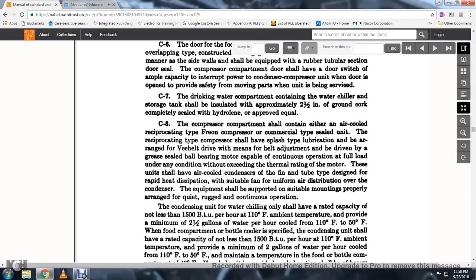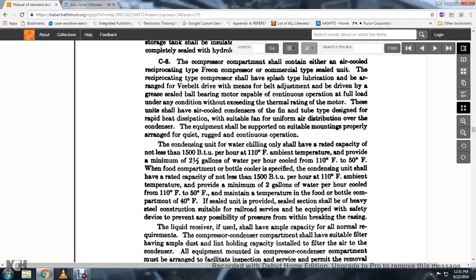These units shall have air-cooled fin and tube type condensers designed for rapid heat dissipation, with a suitable fan for uniform air distribution over the condenser. The equipment shall be supported with suitable mountings, properly arranged to operate ruggedly and continuously. The condensing unit with the water chiller shall be rated at a capacity of not less than 1,500 BTUs per hour at 110 degrees Fahrenheit ambient temperature, and shall cool a minimum of 2.5 gallons of water per hour from 110 degrees Fahrenheit to 50 degrees Fahrenheit. The condensing unit specified with the bottle cooler compartment shall be rated at a capacity of not less than 1,500 BTUs per hour at 110 degrees Fahrenheit.